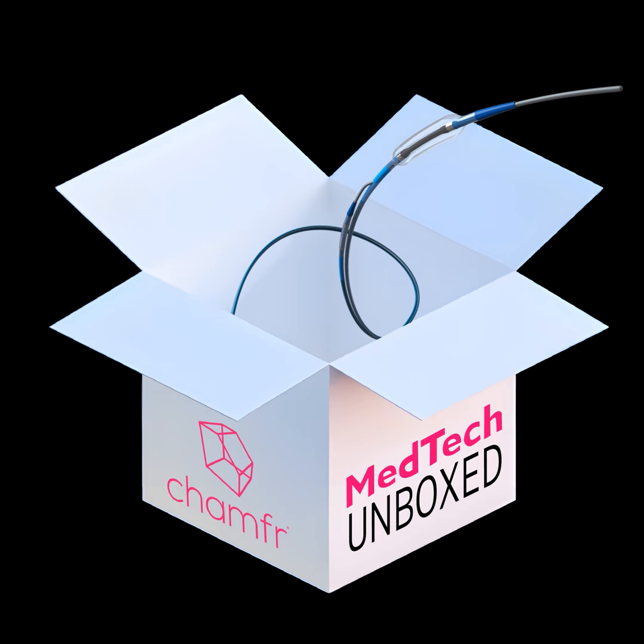So we did a DOE on a liner using PTFE in the very first stage of the development. One thing we realized is that under a tighter bend, when there's a sharper object, whether it's an implant or another laser hypotube or stainless steel feature, rubbing against that PTFE, it will take a dent. But instead of just taking a dent, it will continue to tear out the material. And sometimes some of the fibers will come out because the PTFE strength is being stripped out. So that could be a problem.